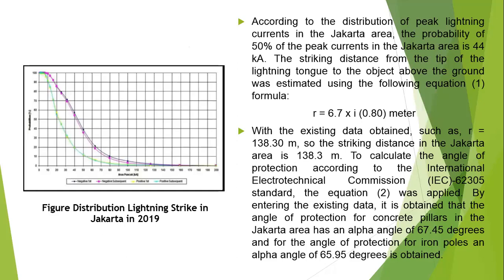According to the distribution of peak lightning currents in the Jakarta area, the probability of 50% of the peak currents in the Jakarta area is 44 kiloampere. The striking distance from the tip of the lightning rod to the object above the ground was estimated using the following formula: R equals 6.7 multiplied by I to the power of 0.8 meter.